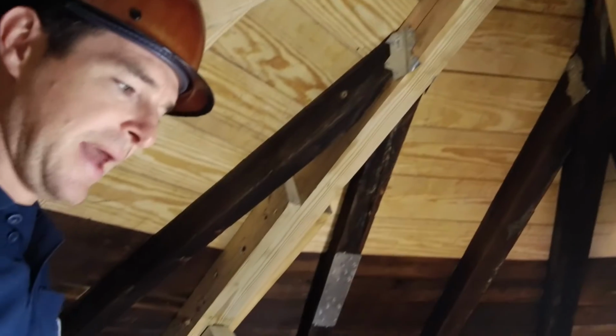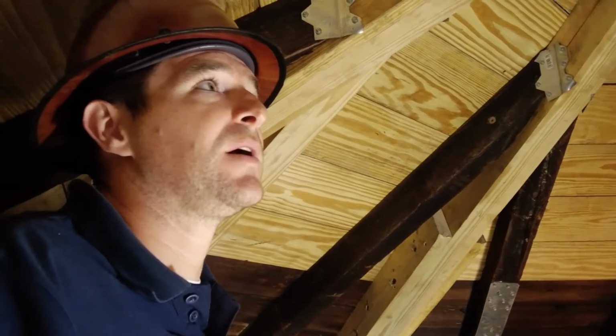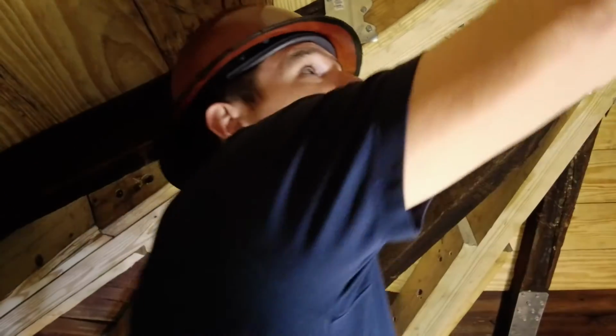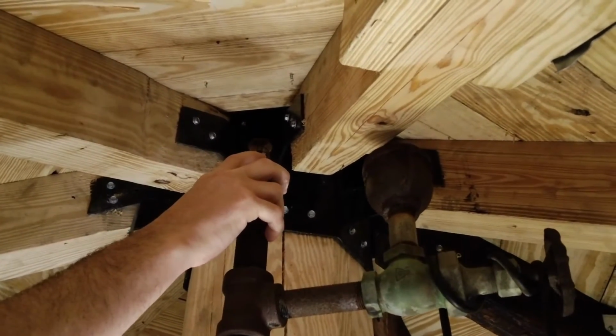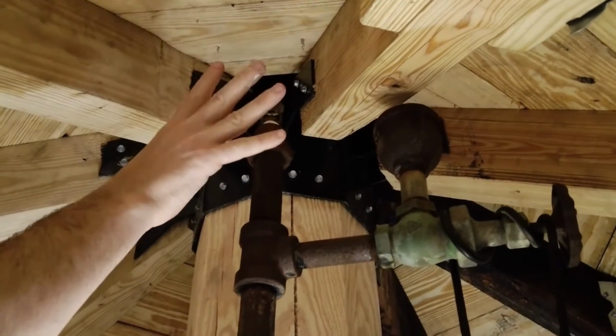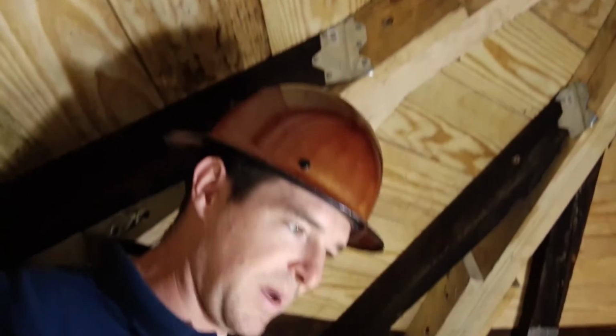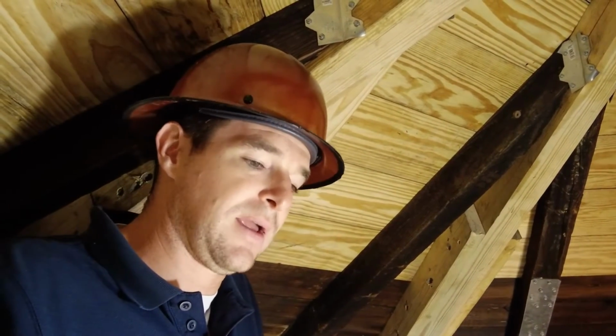But what we are adding as part of the insurance repairs is a sprinkler pump that will go in the boiler room. If any sprinkler heads are triggered like this one was when the actual fire happened, this sprinkler head actually triggered, but there was nothing to come out. Literally the sprinkler head popped and nothing came out of it, and it just kept burning. This fire was put out by firemen carrying portable pressurized water cans all the way up these ladders and stairs.